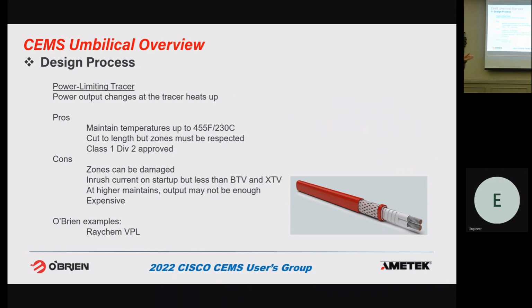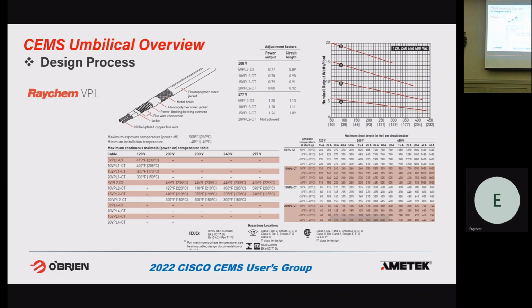But you need to cut the tubing bundle back. You have to cut the outer jacket and insulation, get down to the tracer to find it. So this is a VPL tracer, can maintain up to 455F. But with VPL, it's not a straight 455F. It depends on the individual wattage and voltage.